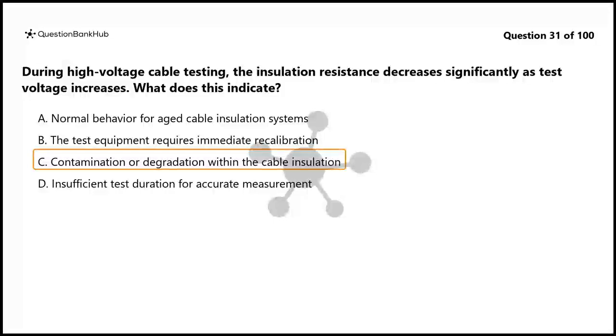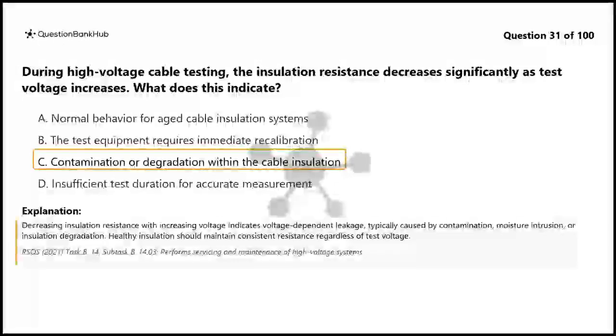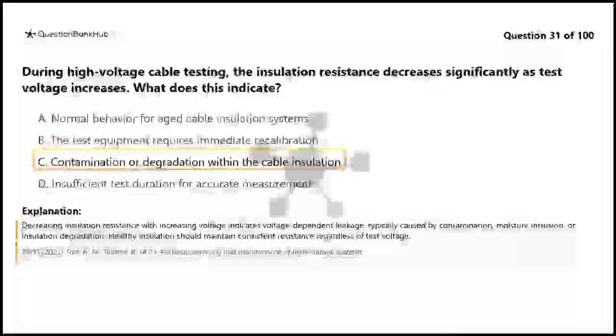The correct answer is C. Contamination or degradation within the cable insulation. Decreasing insulation resistance with increasing voltage indicates voltage-dependent leakage, typically caused by contamination, moisture intrusion, or insulation degradation. Healthy insulation should maintain consistent resistance regardless of test voltage.